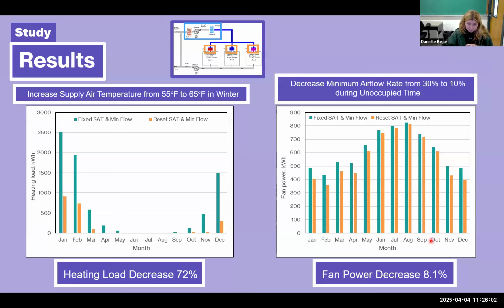So here you can see the results. We have a heating load decrease by 72%. So this is from increasing supply air temperature from 55 degrees Fahrenheit to 65 degrees Fahrenheit in winter. Remember I said the heating load. So heating load means things that are making the space colder. So you have to heat them up. Here we have a supply air temperature that increased. So the heating load decreased, great, by 72%. Then for the fan power, it decreased by 8.1% by decreasing that minimum airflow rate during unoccupied time when we didn't need all of the ventilation that came with 30%. So we saw 8.1% decrease in fan power consumption.